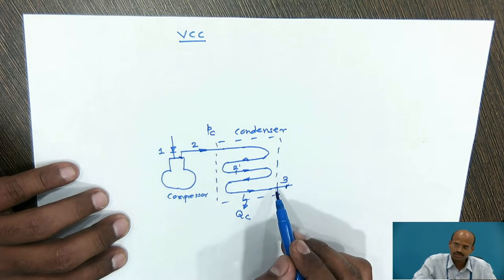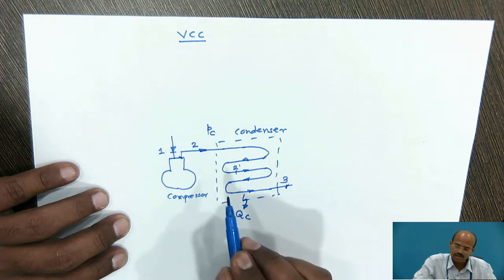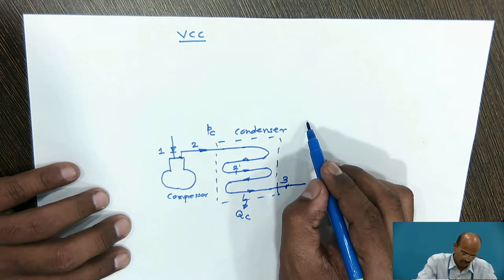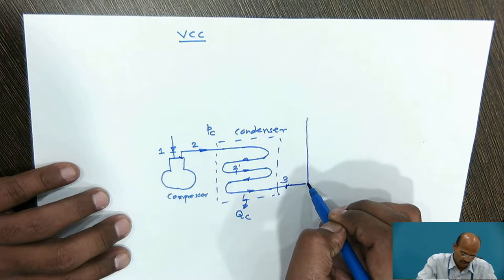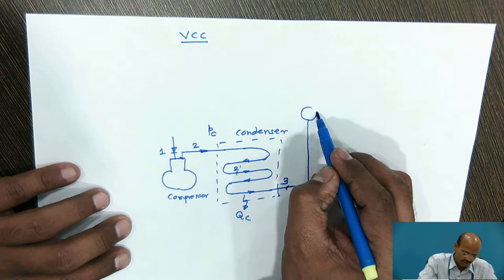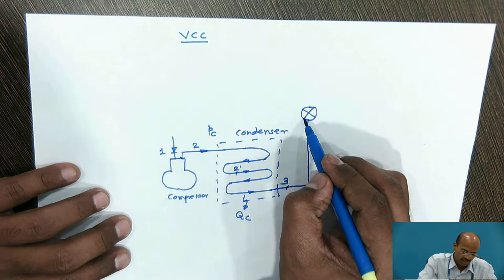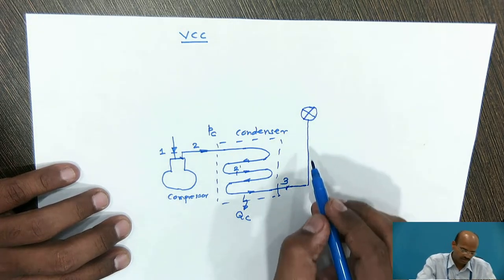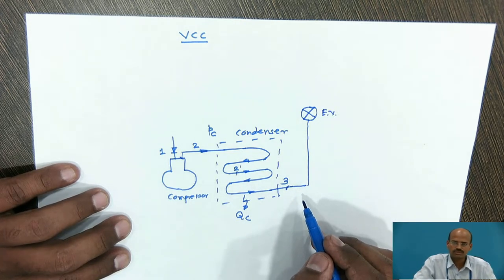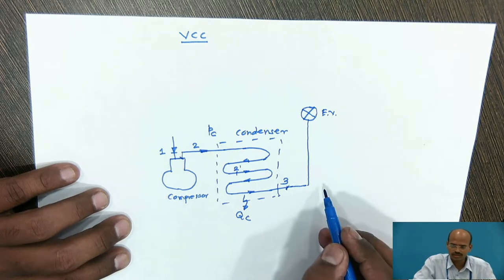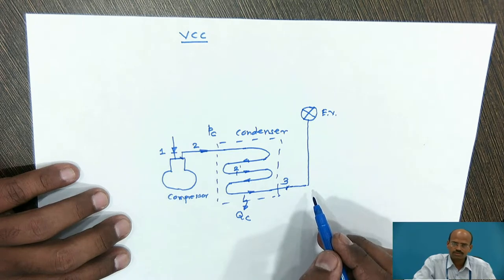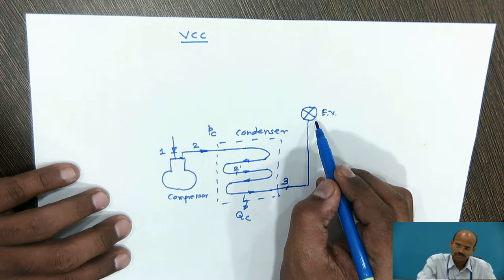The pressure possessed by this refrigerant is high and must be reduced to the designed evaporator temperature. That is why we require an expansion valve. There are different types of expansion valves: the first is the simple capillary tube, second is the thermostatic expansion valve, automatic expansion valve, internally equalized expansion valve, and externally equalized expansion valve.